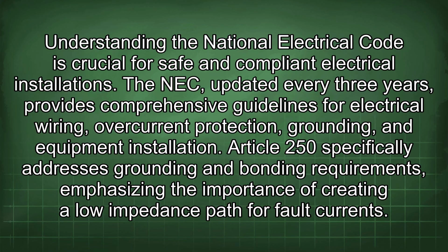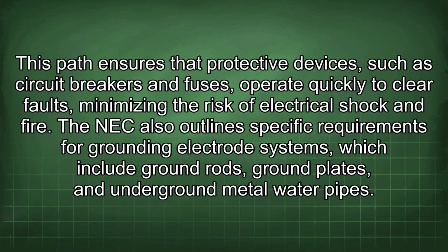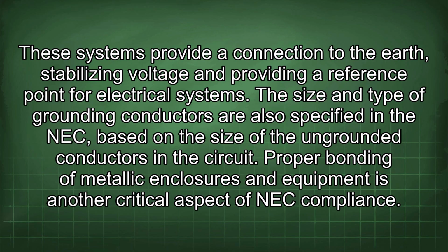The NEC, updated every 3 years, provides comprehensive guidelines for electrical wiring, overcurrent protection, grounding, and equipment installation. Article 250 specifically addresses grounding and bonding requirements, emphasizing the importance of creating a low impedance path for fault currents. This path ensures that protective devices, such as circuit breakers and fuses, operate quickly to clear faults, minimizing the risk of electrical shock and fire. The NEC also outlines specific requirements for grounding electrode systems, which include ground rods, plates, and underground metal water pipes. These systems provide a connection to the earth, stabilizing voltage and providing a reference point for electrical systems.